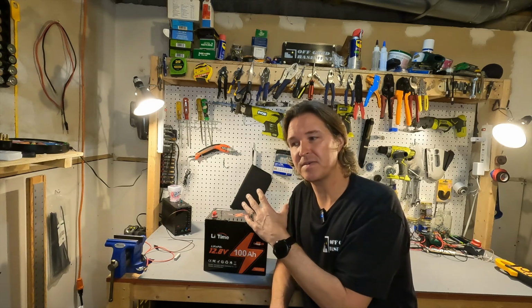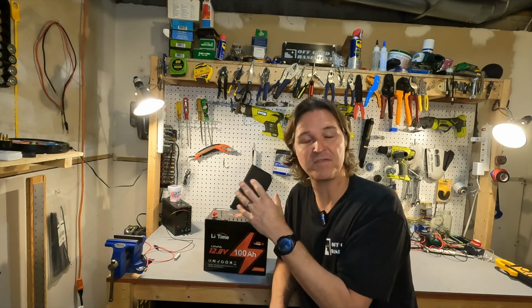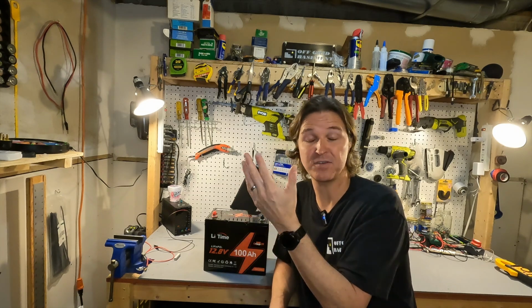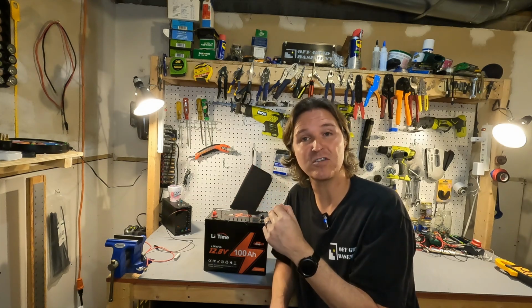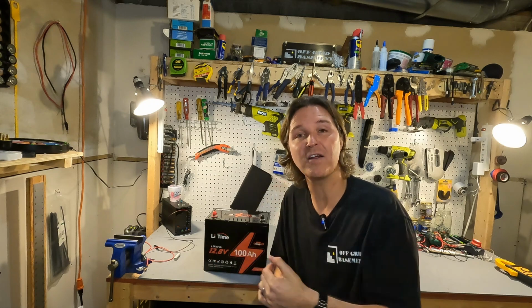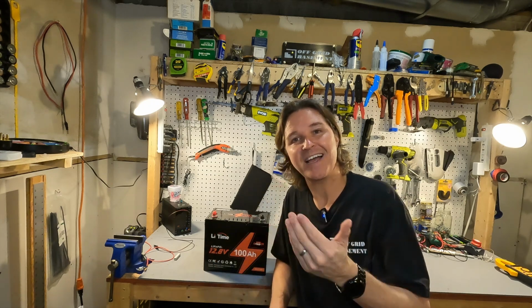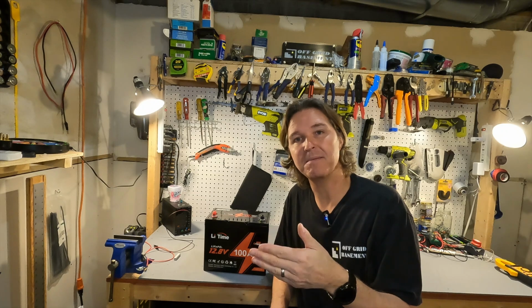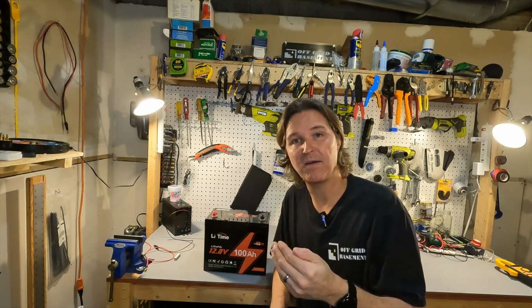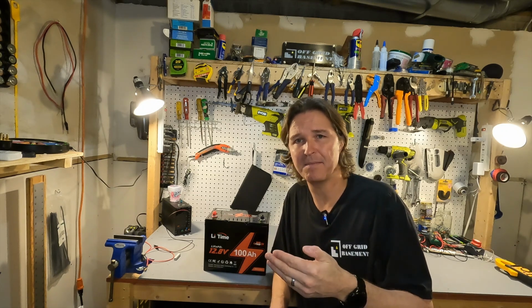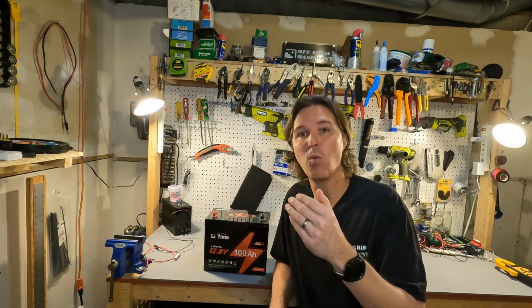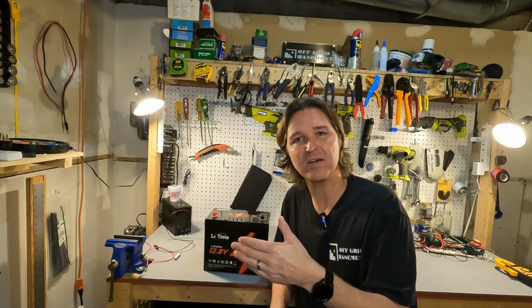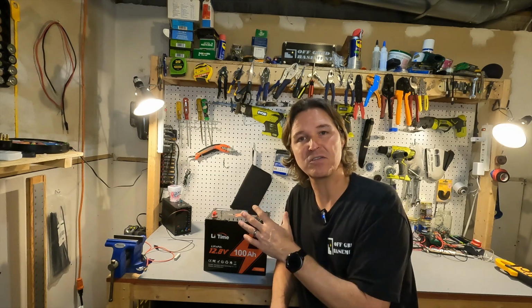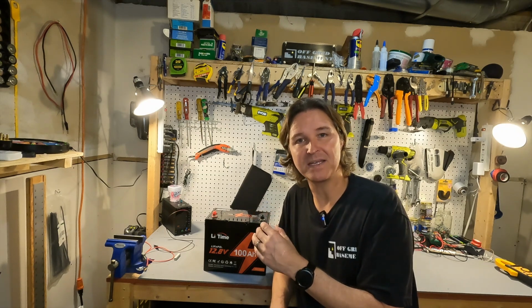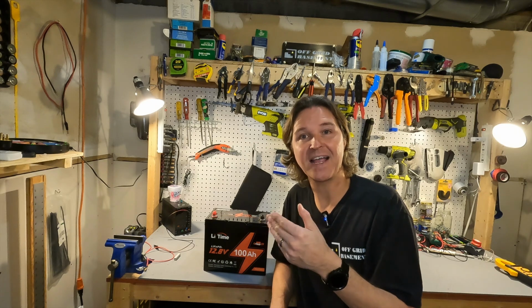You can actually discharge it for over 5 minutes at 100 amps, actually 110, and you can discharge it for a couple minutes at over 200 amps, which that kind of concerns me. I feel like the BMS should shut down after a certain amount of time when you're reaching that way high amperage mark, like that 200 amp mark, because the internals inside, I don't believe, are rated for that kind of continuous draw.